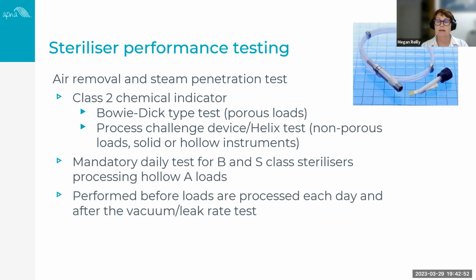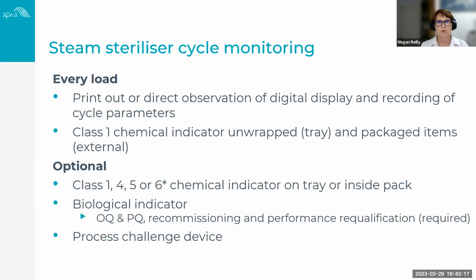This again is a mandatory daily test, but it's only for B-class sterilizers and more modern S-class sterilizers that process hollow A loads. If you don't use hollow A loads, then you won't need to do this test. So it's always performed before the loads are processed each day and after that initial vacuum or leak rate test. So with every load, we need to be monitoring.